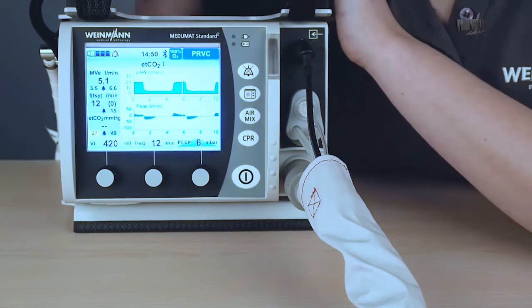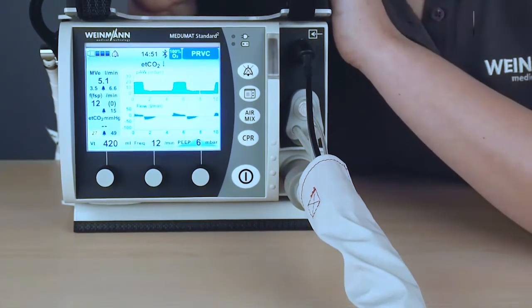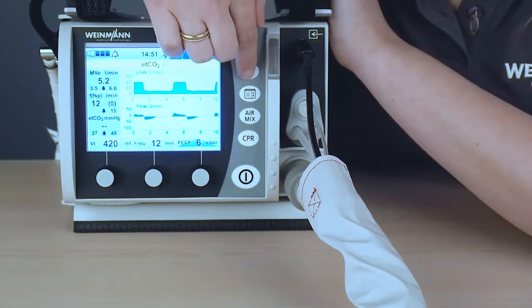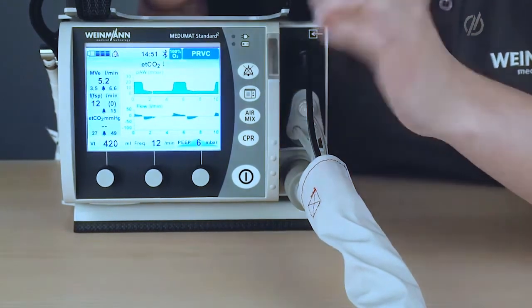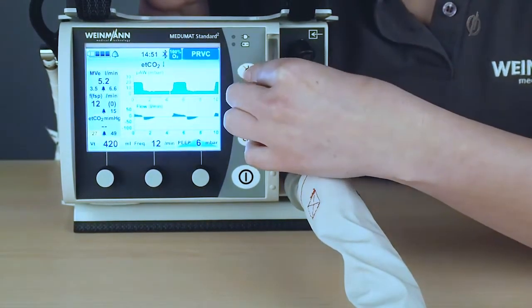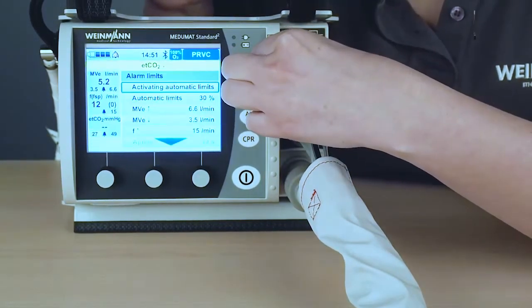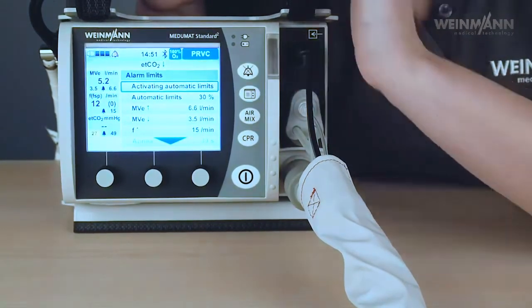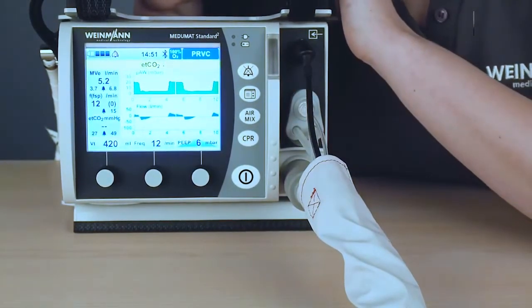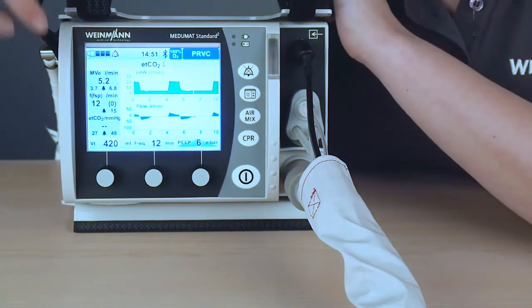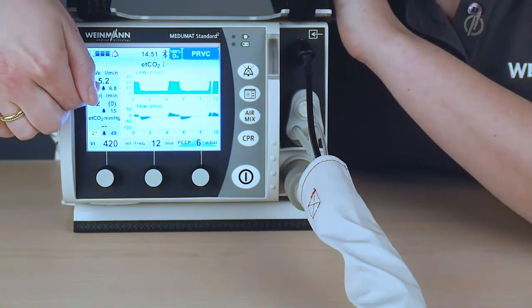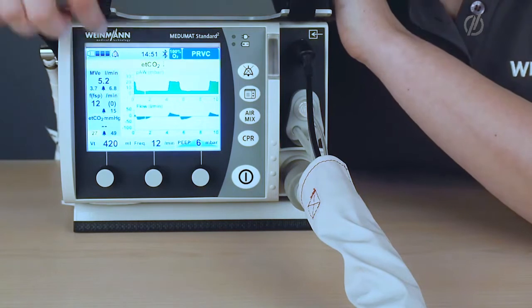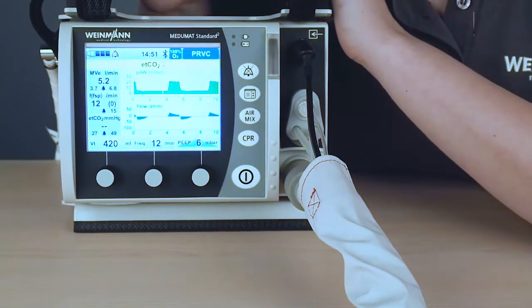In this case now, I have muted the alarm, so a very important function, which is here. So if I press it short, I can mute and unmute the alarms. If I press it long, I have a shortcut to the alarm menu and also to a nice function, which is activate automatic alarm limits. In this case, the device also activates automatically the alarm limits here, depending on the measured value which is displayed.